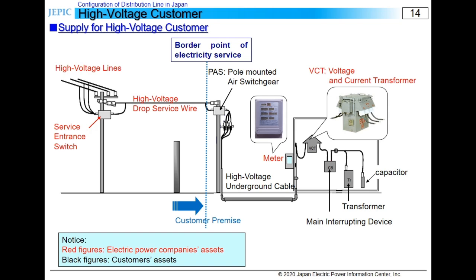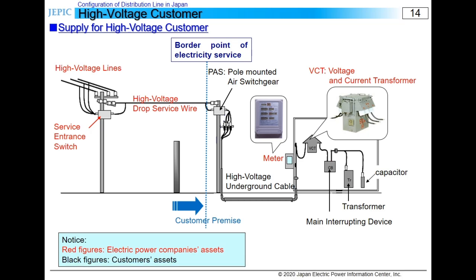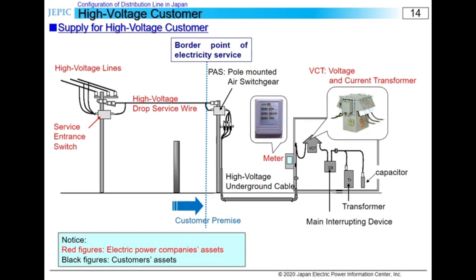PAS can detect a ground fault and a short circuit, and in case of a ground fault, PAS can cut itself before the CB of the substation trips. On the other hand, in case of a short circuit, PAS cannot break a short circuit current, so after detecting a short circuit current, the CB of the feeder once trips. Then electricity is sent again, but PAS won't turn on.